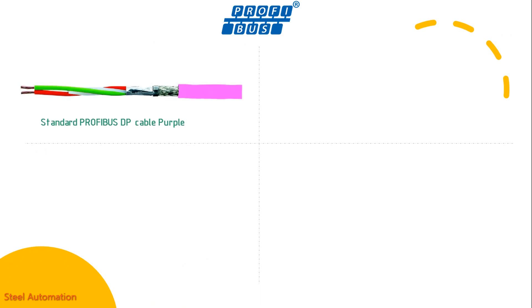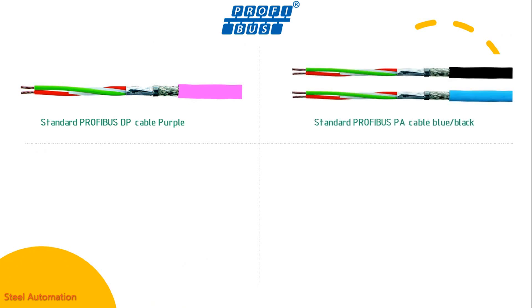Some components are used in relation to Profibus communication. Profibus DP and Profibus PA cables have the same construction but differ in color for identification. The standard outer sheath color for Profibus DP cable is purple, and for Profibus PA cable it is black or blue. It is a special cable having one pair of copper conductors with an aluminum tape and tinned copper drain wire over the inner sheath.